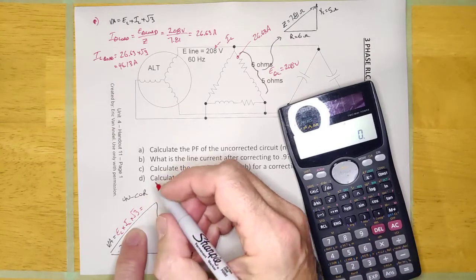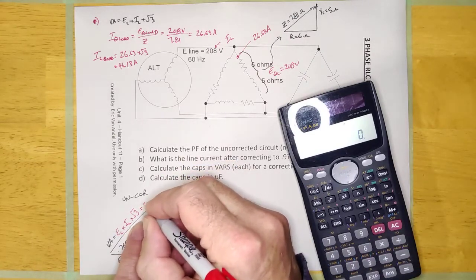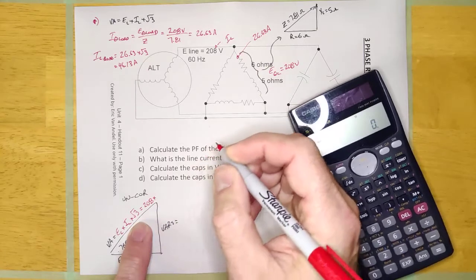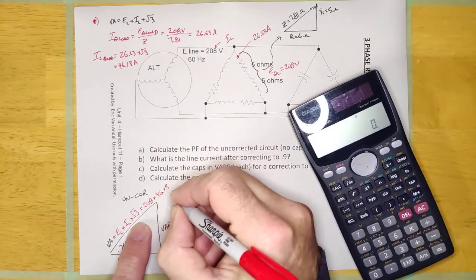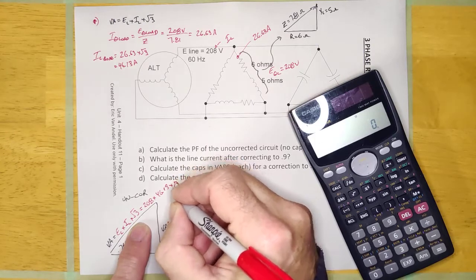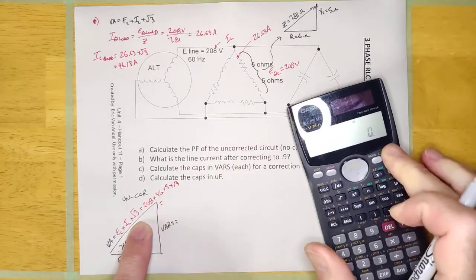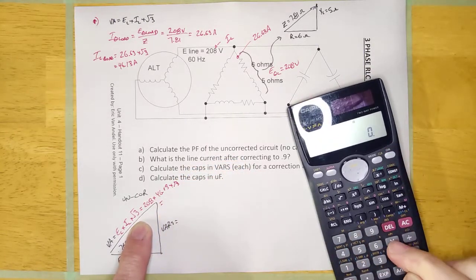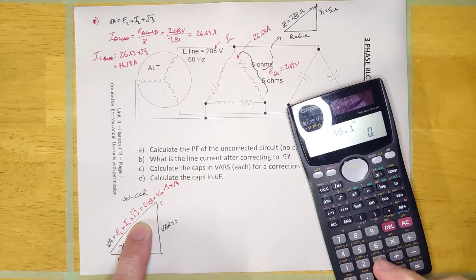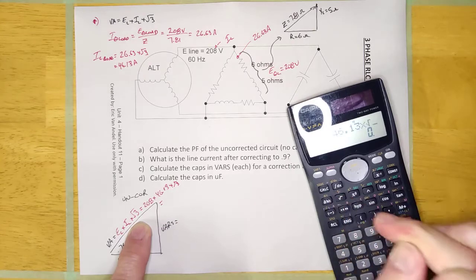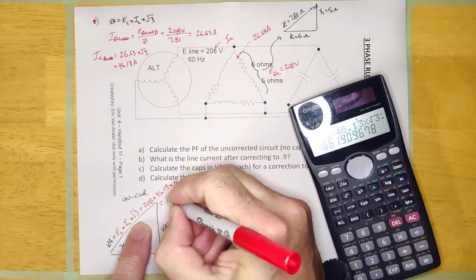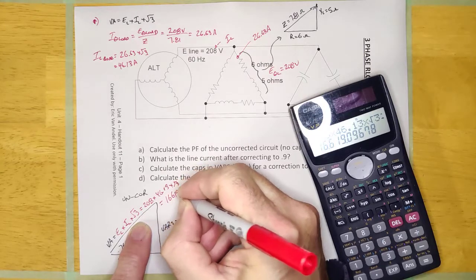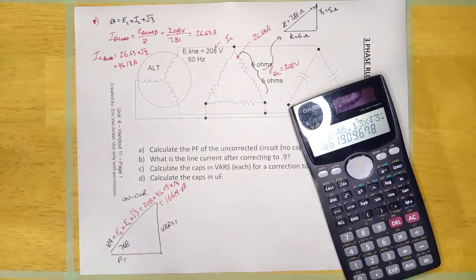And the line voltage is 208, guys. And the line current is 46. And the root 3 because it's three phase. It's going to be 16619 volt amps. All right, guys?